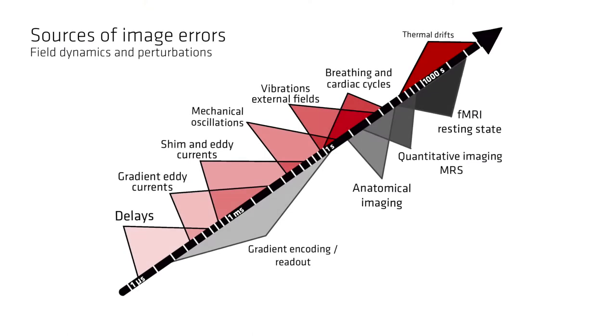There are many sources of system field fluctuations including eddy currents and thermal drifts. Field fluctuations span timescales of microseconds to minutes. The accuracy and precision of the gradient evolution play a key role in determining image quality and geometric consistency as well as the reproducibility and accuracy of derived quantitative results. Not accounting for these perturbations often degrades the value of the images for neuroscientists and clinical researchers.